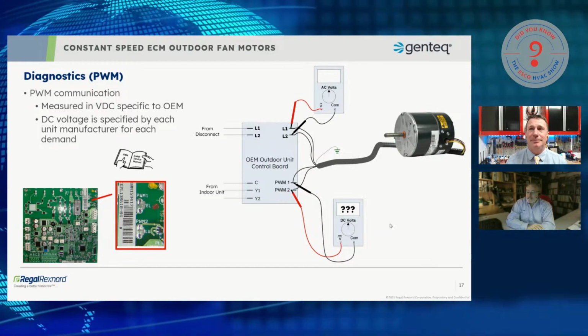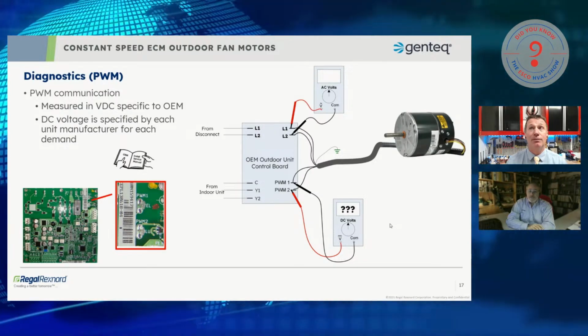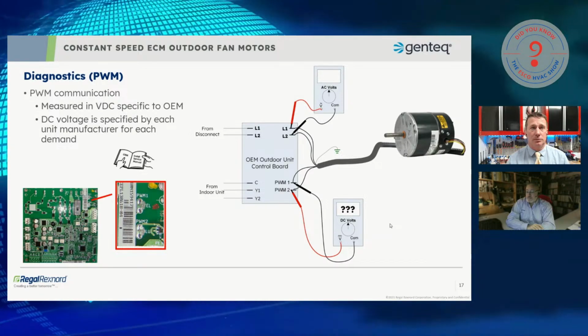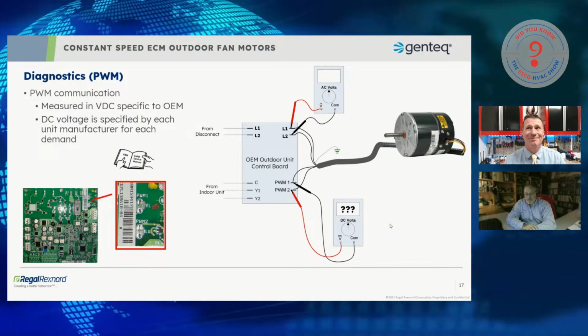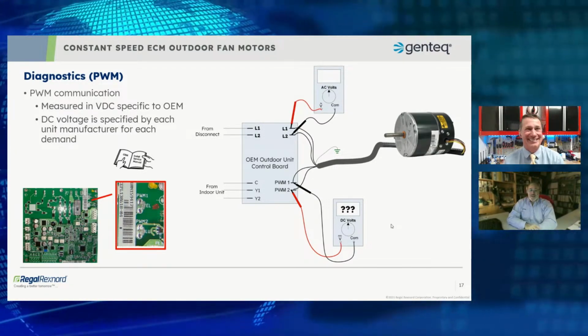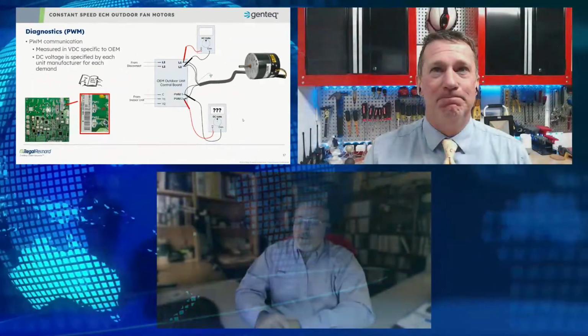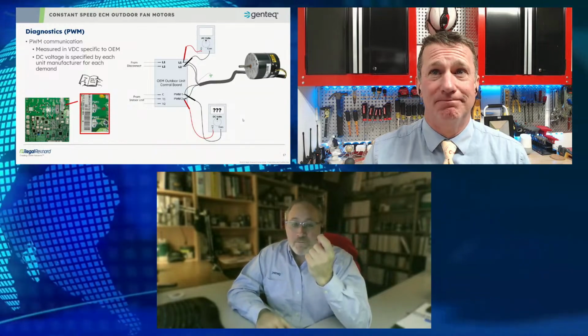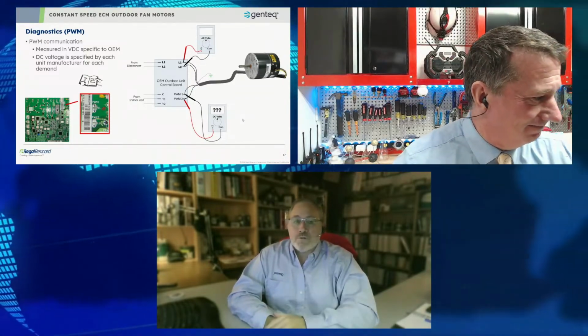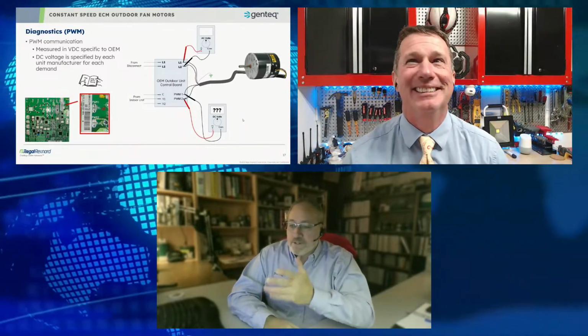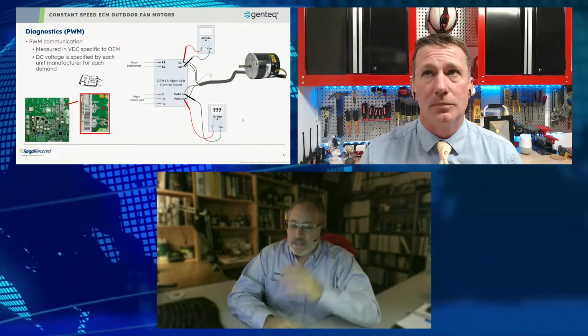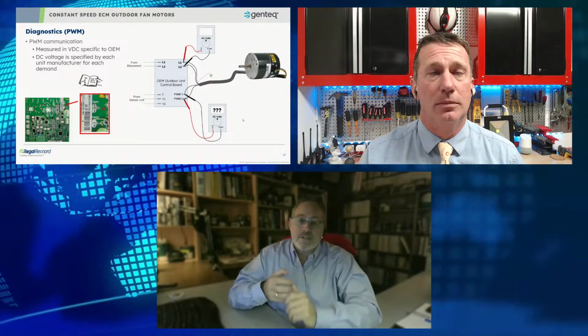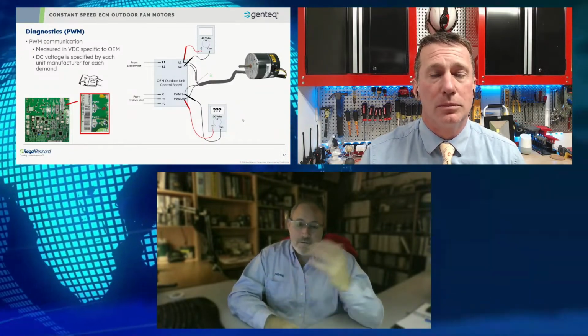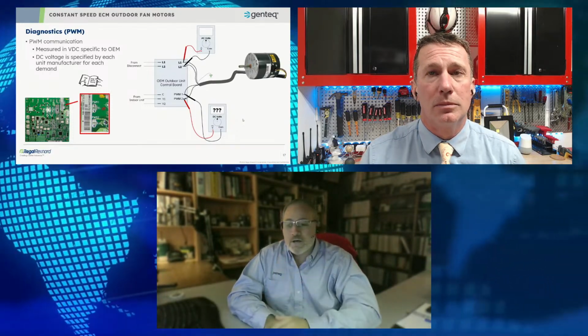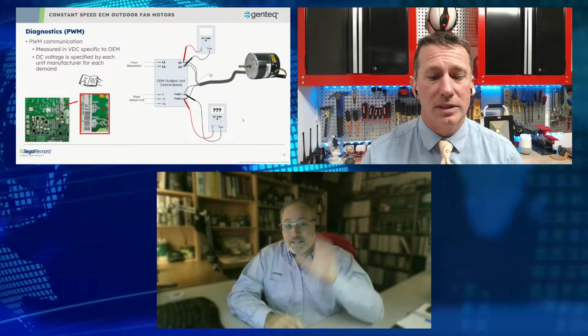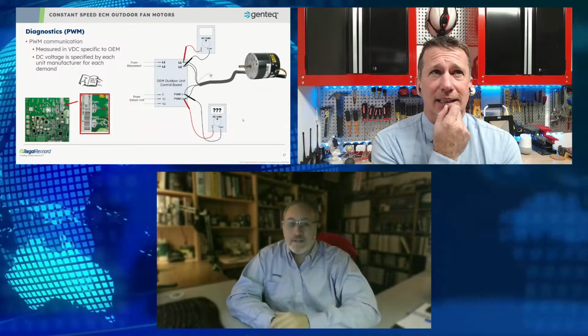Yep. And since you said all that, it's also a good time to reiterate RTFM, read the full manual. If you want to show up to systems and look at the big monster with the ECM and go, I got this. The more you read the manuals, and if I haven't said this in previous webcasts, some of these manuals are 40, 50, 60 some pages. But after you read 1, 2, or 3 manuals, you're going to find out, especially if it's just the motor operation, it's the same 3 pages in any manual. You're looking for the performance charts, you're looking for the diagnostics for either the PWM signals or what the tap terminal designations are, if it's not on the door on the schematic. You'll find yourself, especially if you get PDFs, just scrolling until you see that page with all the performance charts on it, or the wiring diagram. That's exactly what you need.